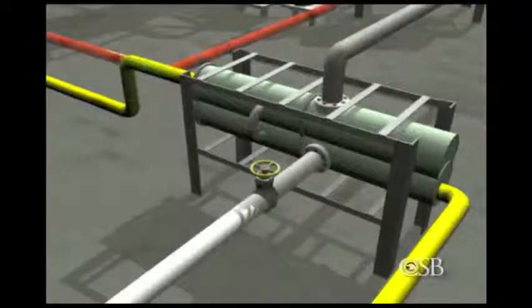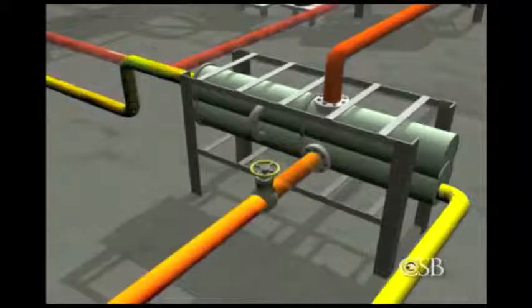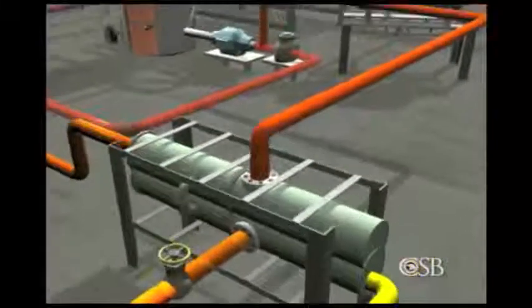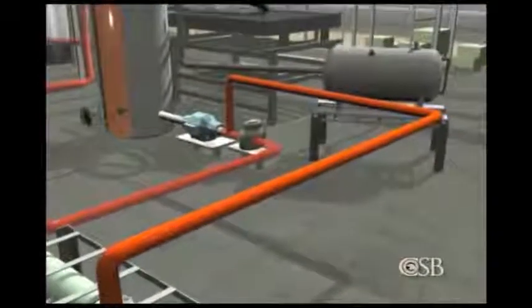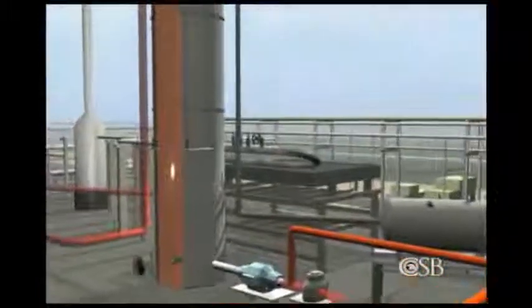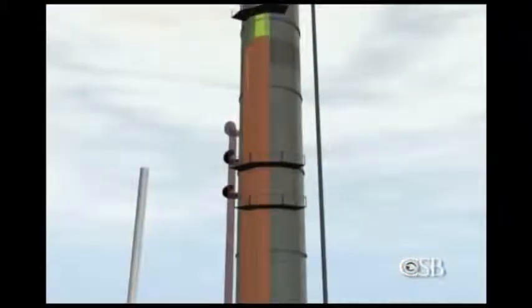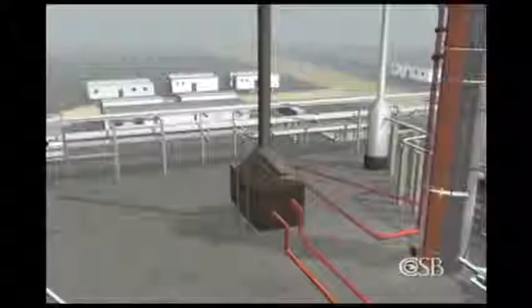The operators did become concerned about the lack of flow out of the tower and began opening the valve to send liquid from the bottom of the tower to storage tanks. But this liquid was very hot. As it flowed through the heat exchanger, it suddenly raised the temperature of the liquid entering high up the tower by 141 degrees Fahrenheit. It was now about 1 p.m.